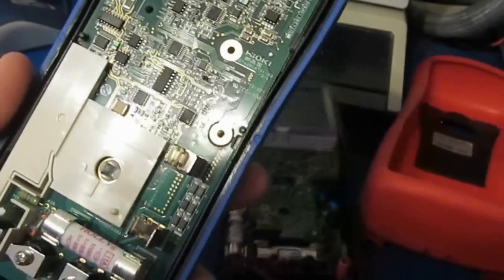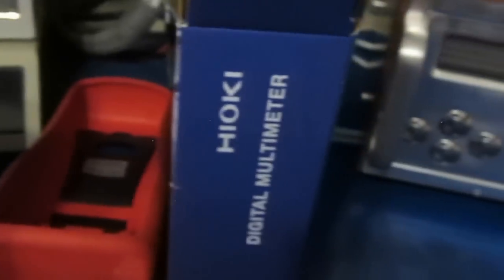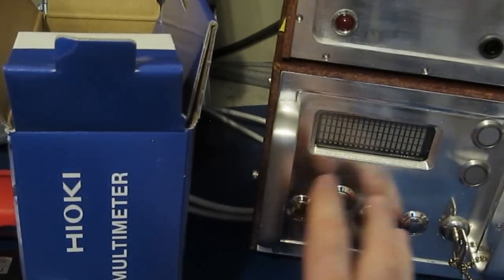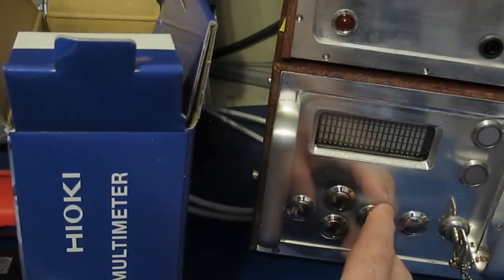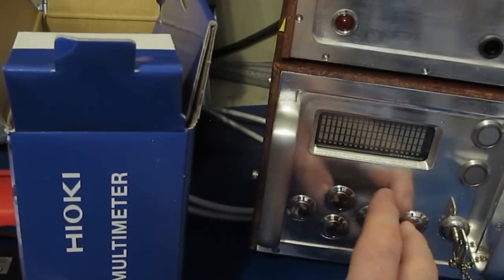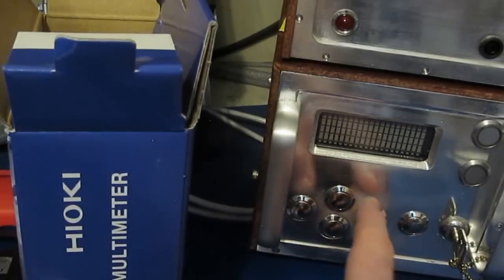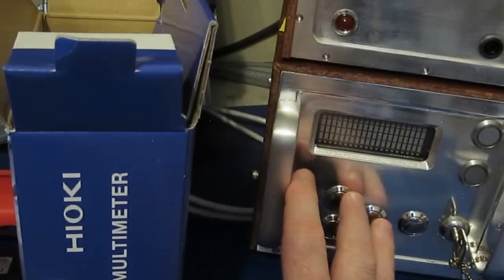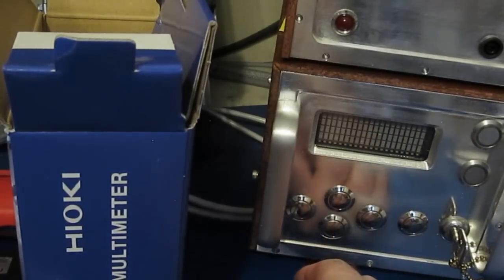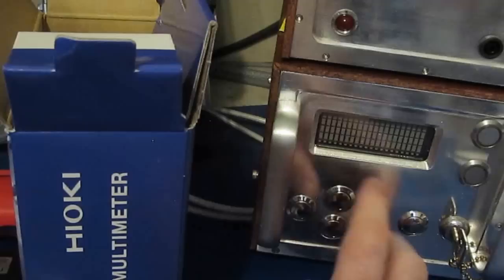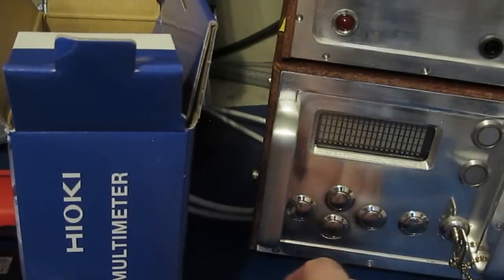Now, one thing to mention is that these transient generators are very low energy, so I'm testing somewhere below about 20 joules with this generator. I want to be clear this has nothing to do with the IEC standards and the actual surge tests performed on these meters for safety testing. This testing has nothing to do with safety. What I'm looking at here is how electrically robust these meters are.